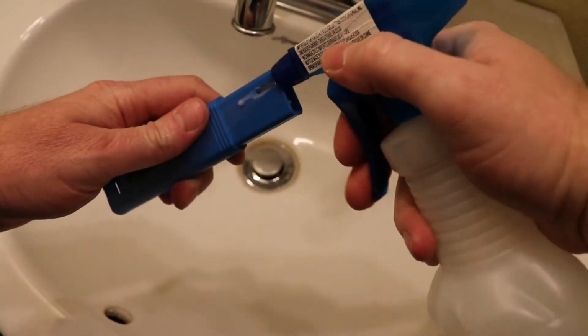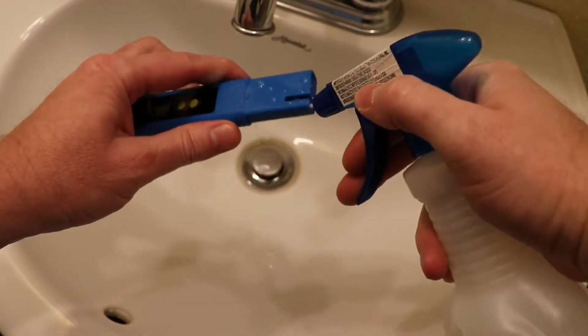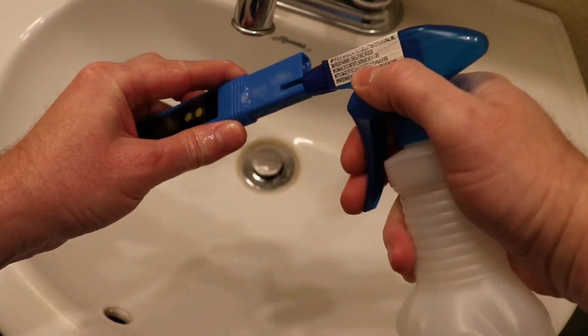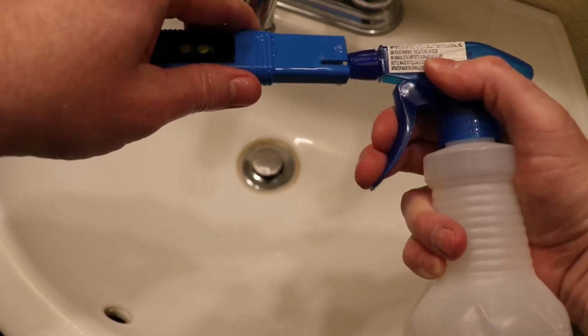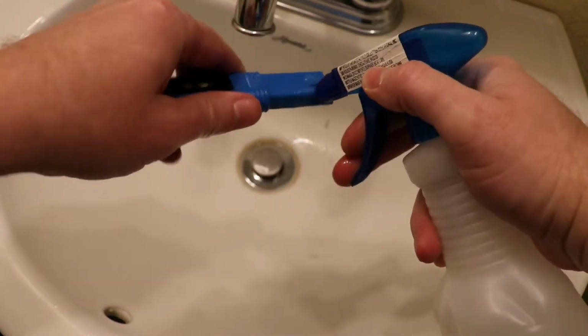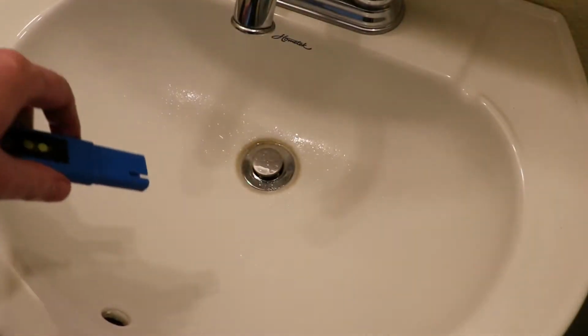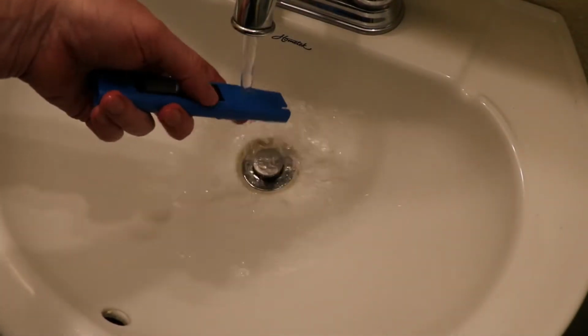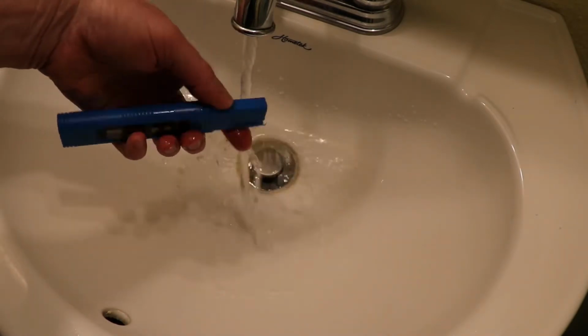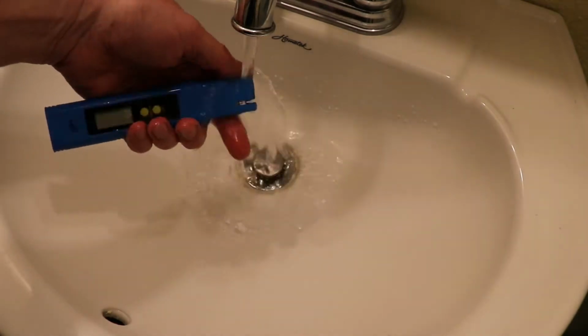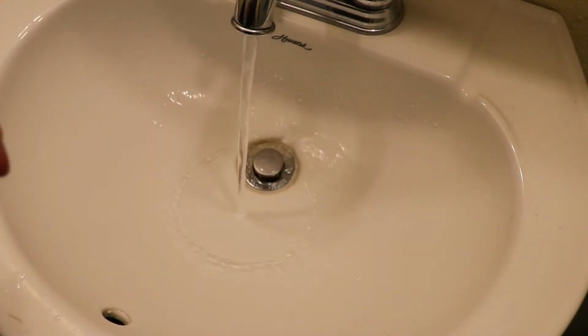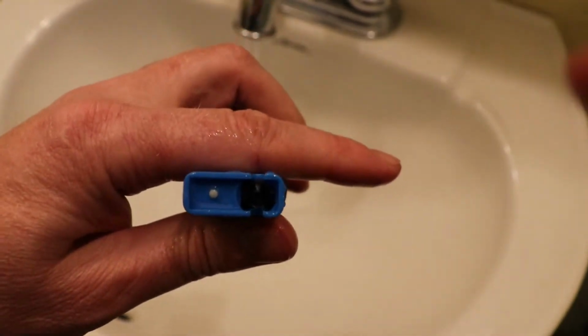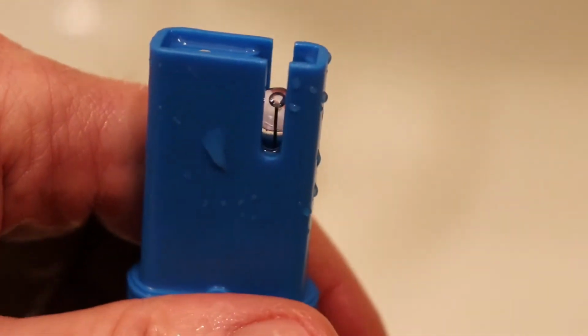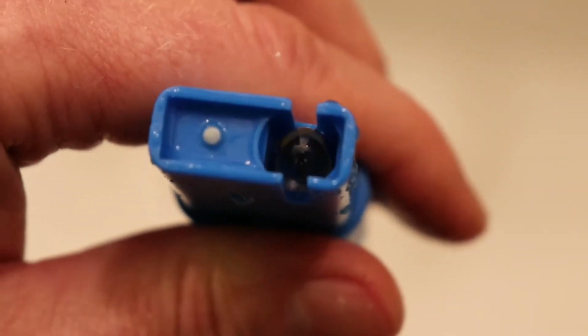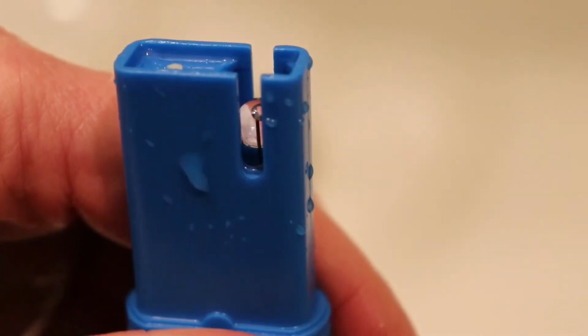This is some 99% isopropyl alcohol, and just spray the living bejeebus out of this little bulb in there, because stuff gets built up in there, and you have to clean all the grease and salts and stuff like that off. Then run it under hot tap water. Let the tap water get as hot as your water heater will go to help dissolve anything that's on this little bulb right there. And I've soaked this thing overnight in distilled water and still had the error message when I tried to calibrate this.